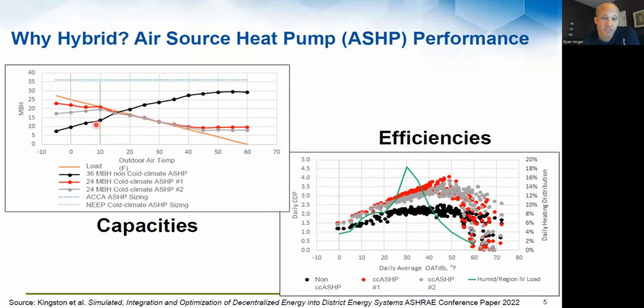The black line was a traditional air source heat pump, how efficient it was, or excuse me, how many BTUs it can make. And as it gets colder, it makes less and less. That was a 3-ton traditional, black in black. And then red was a smaller 2-ton cold climate, and gray was a smaller, different model of 2-ton cold climate. So both of these cold climate ones have less BTU ability at their design point for cooling than the one up here in black. But as you could expect, this one here is dropping its BTU capacity, like we showed 2 weeks ago or 2 modules ago, as the outdoor air temperature drops until we get to this point right here, and it can't handle it anymore. In this case, instead of putting in a new 3-ton cold climate, it was downsized to a 2-ton.